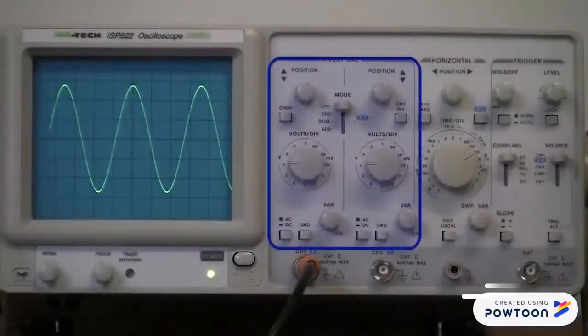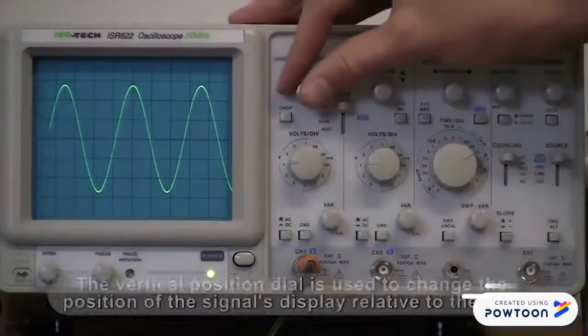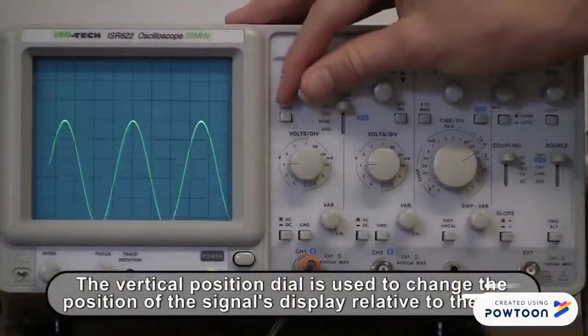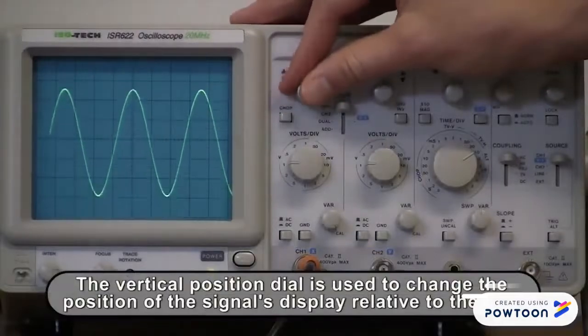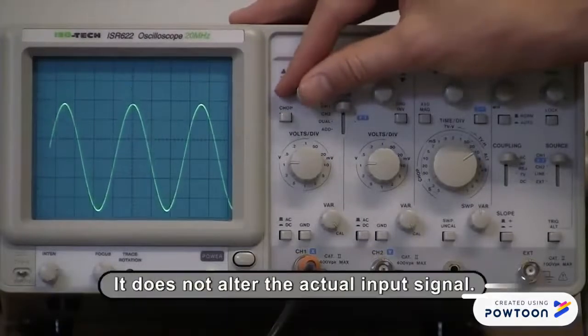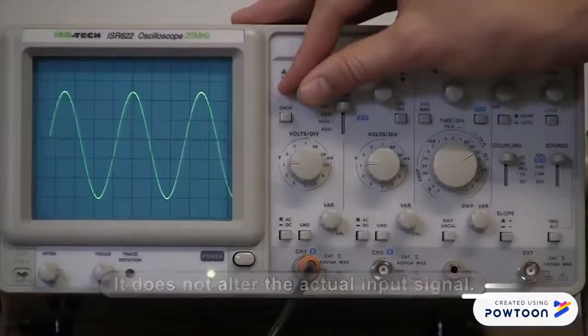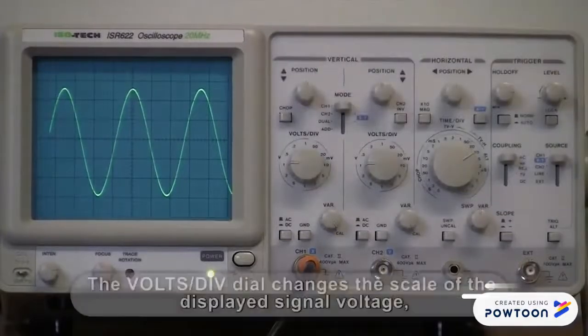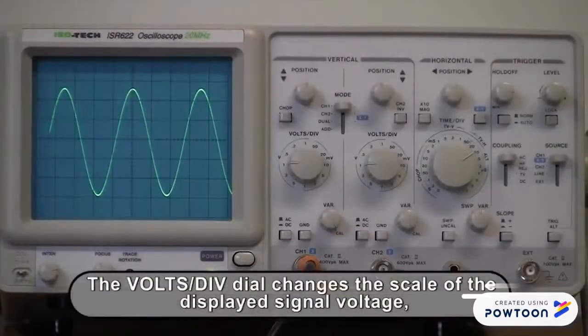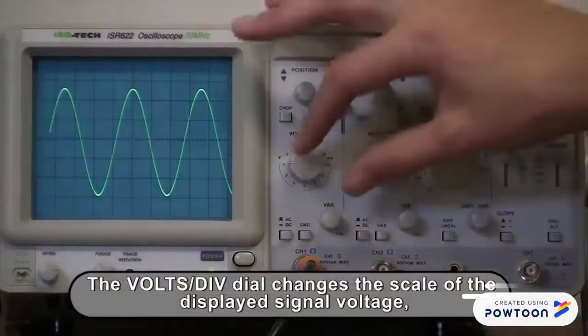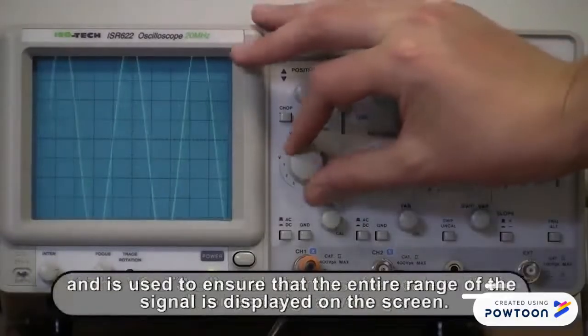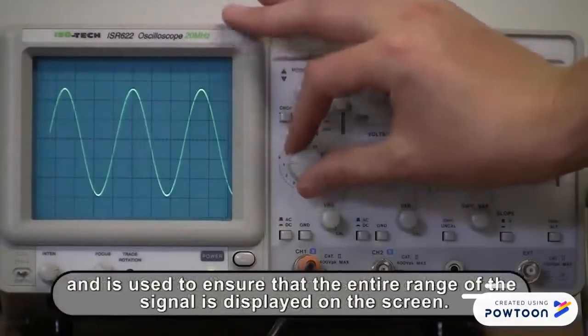The set of controls on the left of the oscilloscope vary the position and scaling of the vertical or voltage axis of the signal displayed on the oscilloscope screen. The vertical position dial is used to change the position of the signal's display relative to the grid. It does not alter the actual input signal. The volts per division dial changes the scale of the displayed signal voltage and can be used to ensure that the entire range of the signal is displayed on the screen.